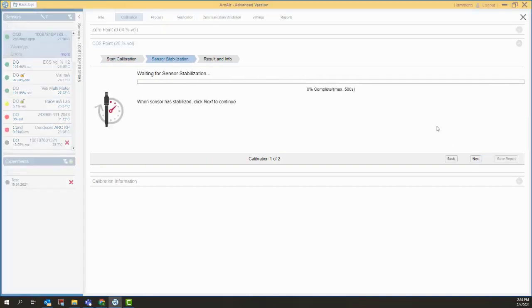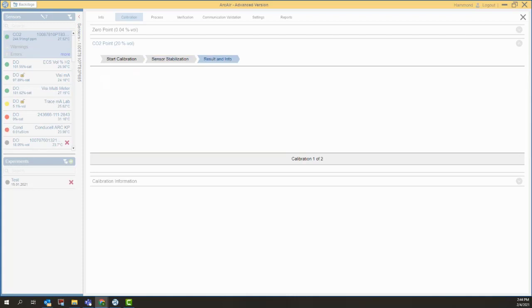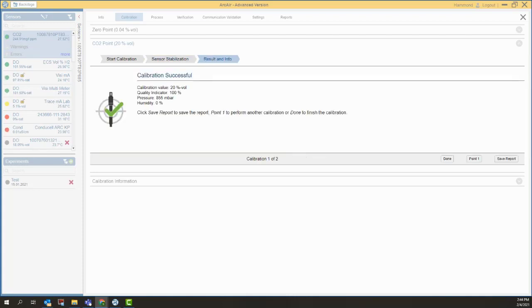So I'm going to click start here, and we're going to go through the same process here. So the sensor is going to stabilize, and it's going to take readings throughout the calibration for about 500 seconds here. So I'm going to let this run for a bit, and then we'll come back at the end. And now we're just wrapping up our 20% by volume CO2 point calibration. So it's about complete here. And I get my final message here that says calibration successful.